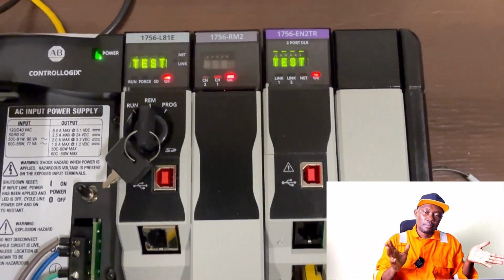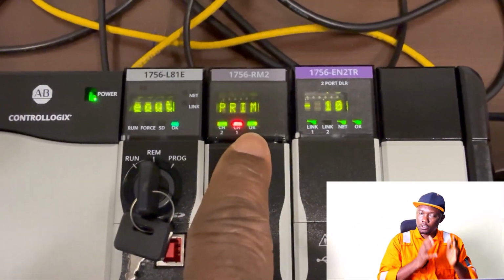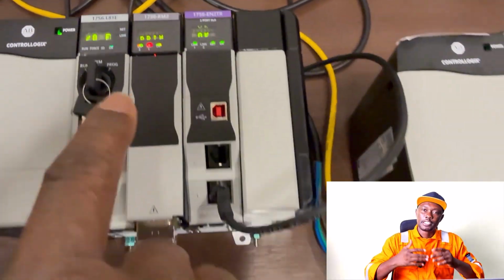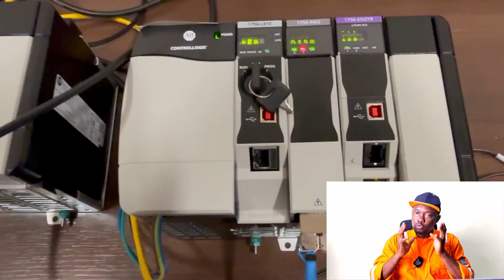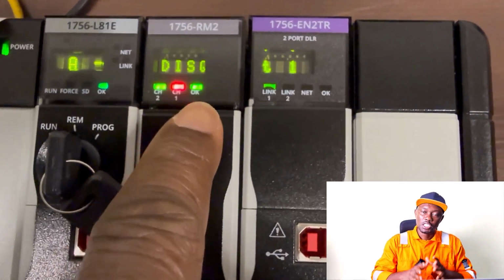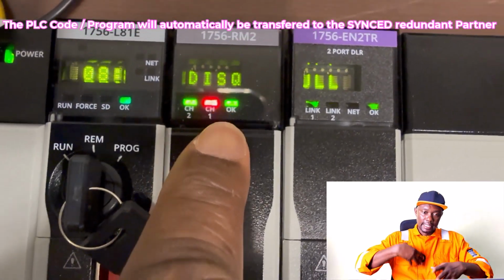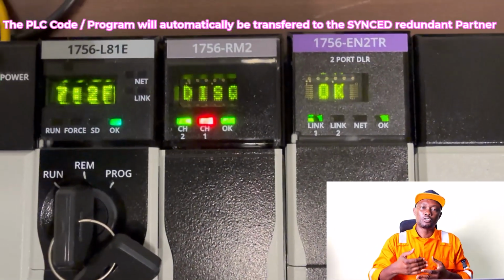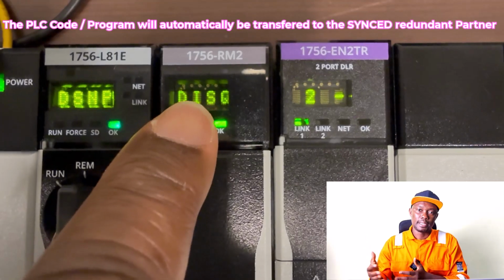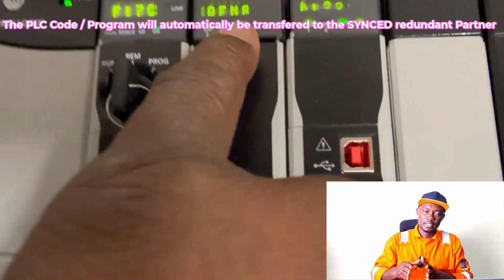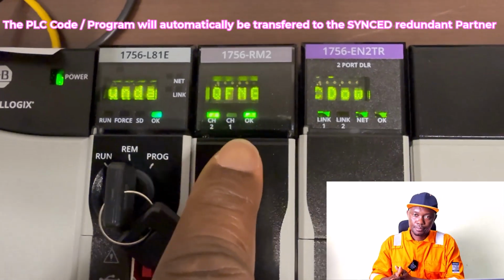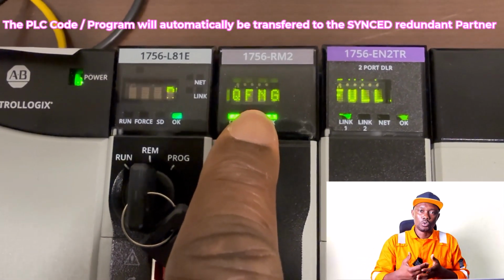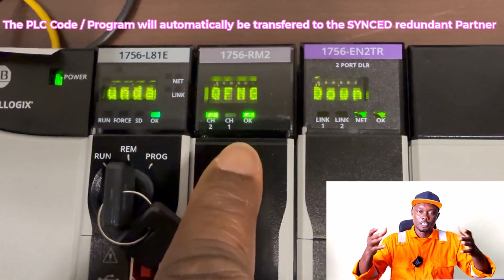The one that is primary, which you've downloaded, will be showing PRIM. Then the secondary will show, at the initial time, disqualified, DISQ. It's now starting a process of qualifying and getting synchronized. So from disqualified, you will now see qualifying, because it's trying to qualify and synchronize with the partner.